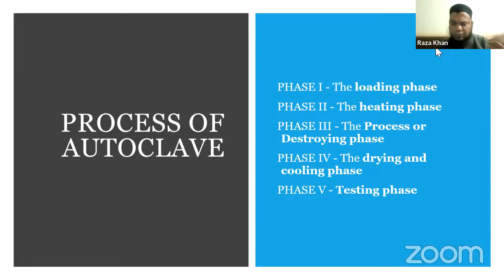The loading phase requires various steps: decontamination of instruments, disassembly of instruments, sorting out all instruments properly, checking of instruments, then washing and disinfecting, drying, packing, and then loading into the sterilizer. All these steps are required in the loading phase. The testing phase is very essential, because without testing we cannot be sure whether sterilization has been done or not. We use various types of testing for autoclaves.